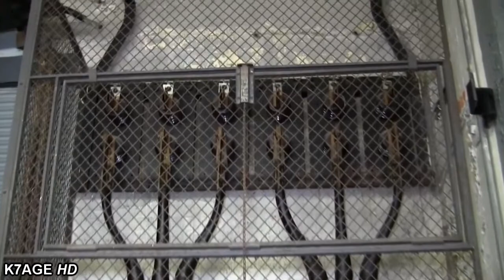33 kilovolts primary power, stepped down to 2400 volts, with dual feeders, came into the building right here on cable A and cable B. From there, the power was routed over here to these oil breakers, which had the ability to cut the power in literally a cycle or two of the AC sine wave. That then fed AC back out to the plate transformers, which were on the pad behind the building.